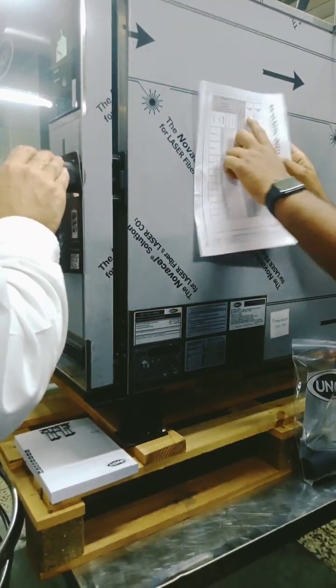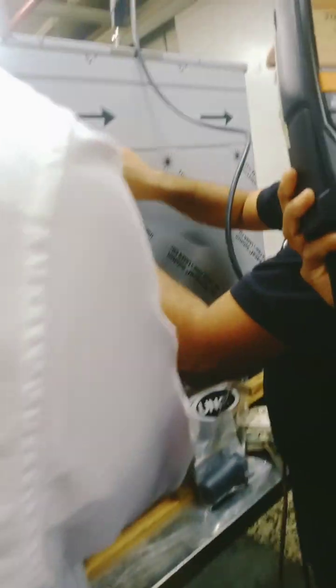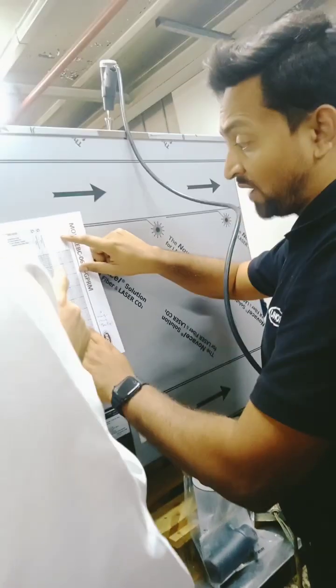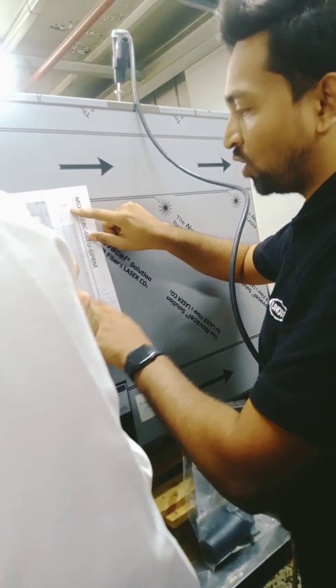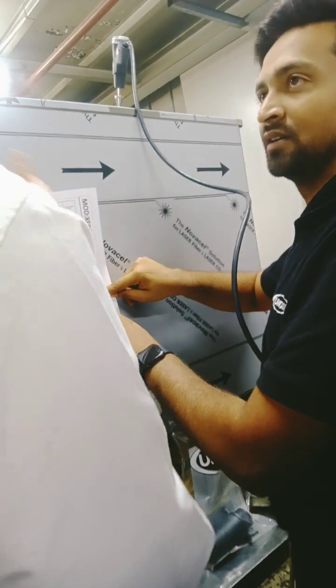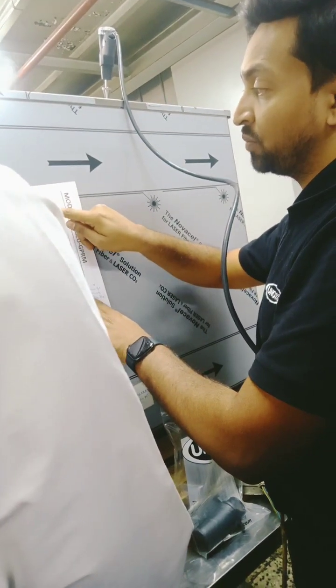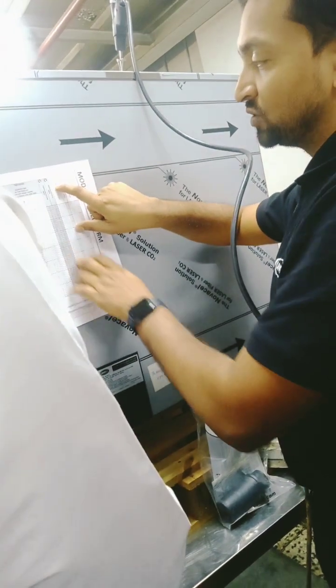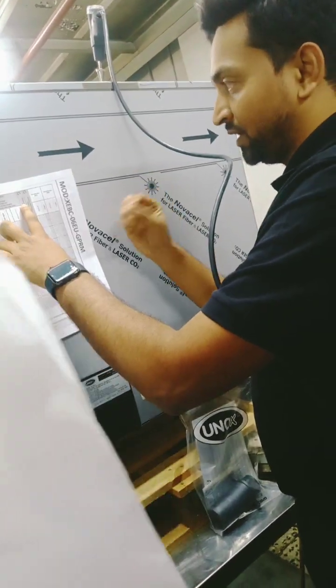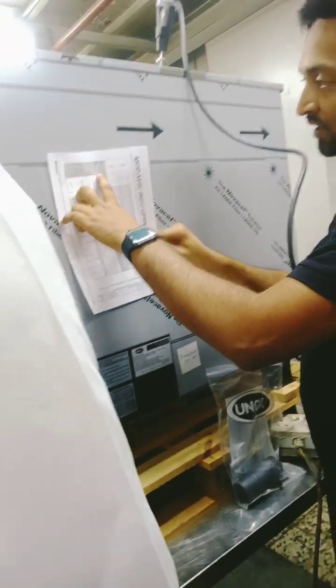Test one. See, here it is written test one. I press test one there. Again, test if these values meet these ranges. Test two is automatic, it will come between these ranges. Very good. So we need to concentrate more on maximum combustion. Maximum combustion is the most important. If maximum combustion is within the value, then minimum is automatically in the value.